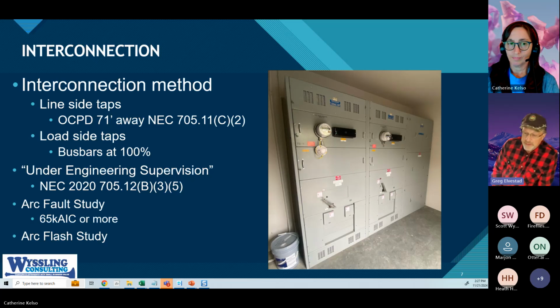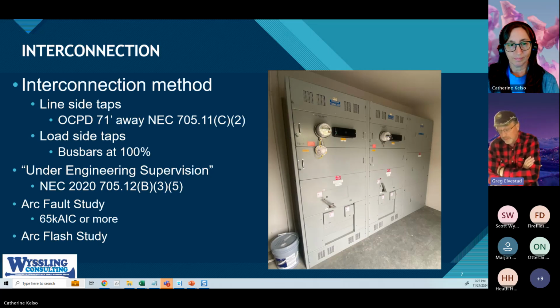Another option is making a load side tap on the bus, taking bus bars at 100%, which, if you do residential, there's the single point of interconnection rating that matches the bus bar. In some circles, it's known as a Hawaiian tie-in, if you will. Commercial-wise, it gets a little bit different, because usually the PV interconnection is not the only device that's connected to the bus. So it makes it weird.